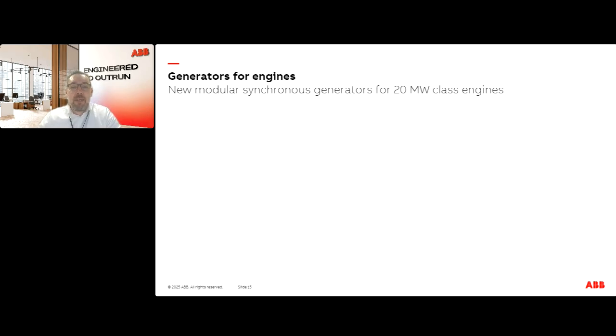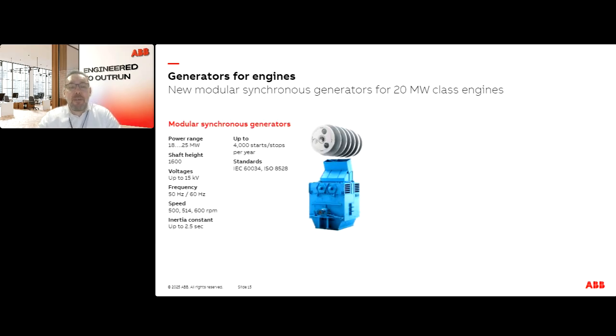Going a bit deeper into the technical details of this new modular synchronous generator - it's designed for 20 megawatt class engines, meaning power range is roughly 18 to 25 megawatts. Voltage is up to 15 kilovolts, and typical frequencies are 50 hertz and 60 hertz. The biggest innovation here is the capability to have flywheels to increase the inertia, which helps comply with even the most demanding grid codes. Let's go through that in the next slides.